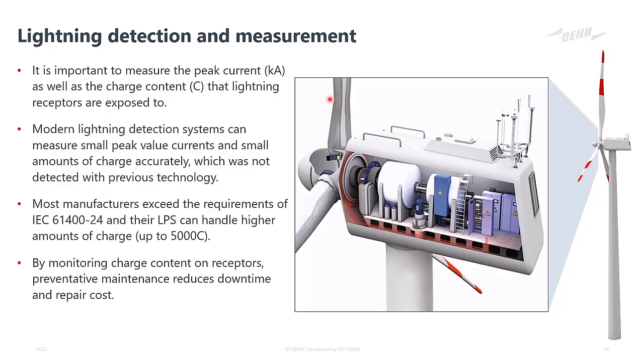And these detection systems have advanced so much that they can measure even the smallest amounts of current and charge, which was not possible to be picked up with older technology. And this makes the system very accurate. Now, this system is then adjusted to what your turbine is rated for. Now, the standard requirements, as we said, is 300 coulombs for a single event or 900 accumulated. But some manufacturers we see nowadays can go up to 5,000 coulombs accumulated charge. And again, if you start exceeding 5,000 coulombs, you will start having catastrophic damage. So it's important to measure that by means of a lightning detection system.